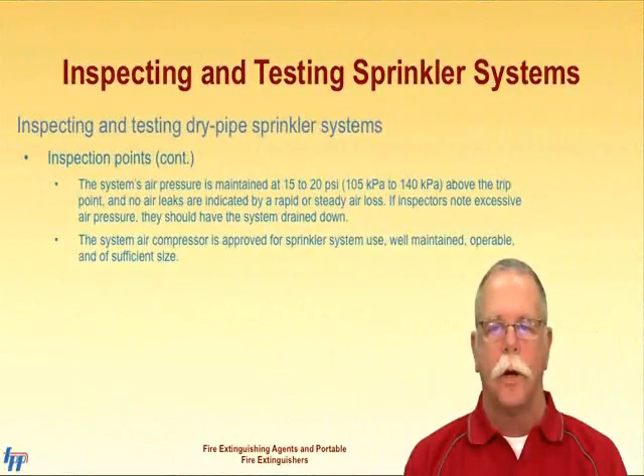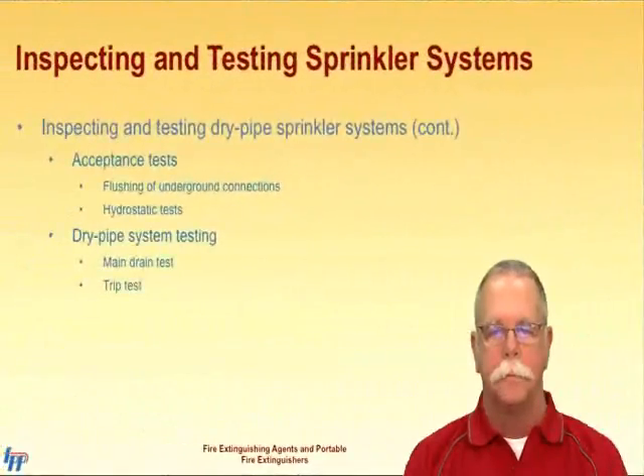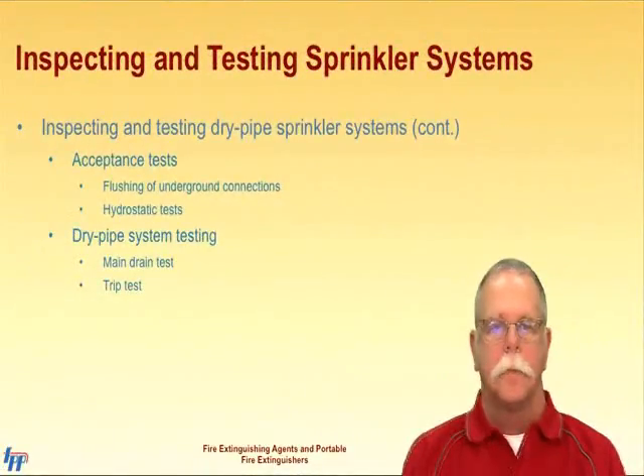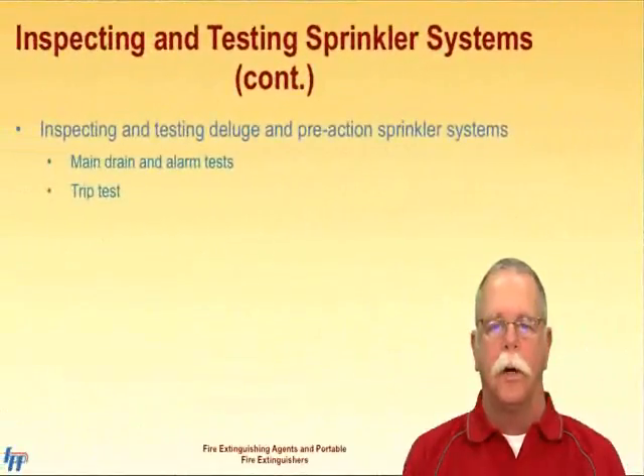Testing and inspection of dry pipe systems is similar to the testing and inspection of wet pipe systems, but has some additional steps regarding the system that keeps them dry. Inspection and testing of deluge and pre-action systems is the same as for wet and dry pipe systems. However, it should be inspected monthly, or even weekly or daily during freezing conditions. The detection system should be tested twice yearly, and the system itself should be actuated and tripped annually.